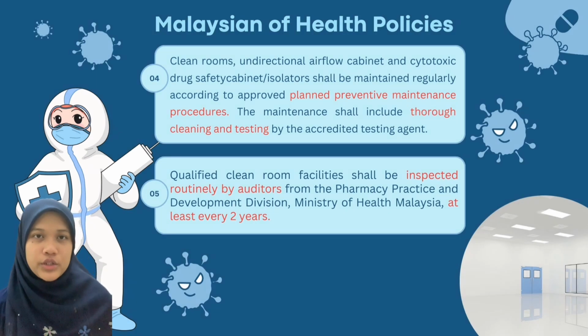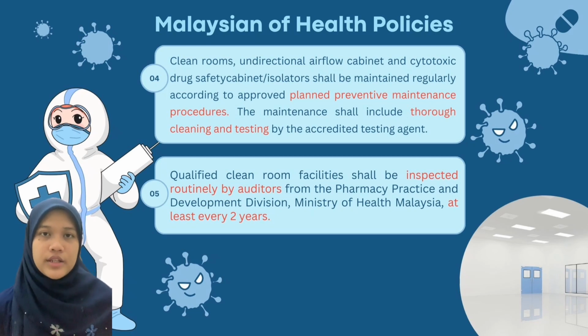Next, clean rooms, directional airflow cabinet and cytotoxic drug safety cabinet or isolators shall be maintained regularly according to approved preventive maintenance procedures. The maintenance shall include thorough cleaning and testing by the accredited testing agent. Hence, microbial monitoring shall be done regularly depending on the usage of the facilities and outcome of the test result. Lastly, qualified clean room facilities shall be inspected routinely by auditors from the Pharmacy Practice and Development Division, Ministry of Health, Malaysia, at least every 2 years.